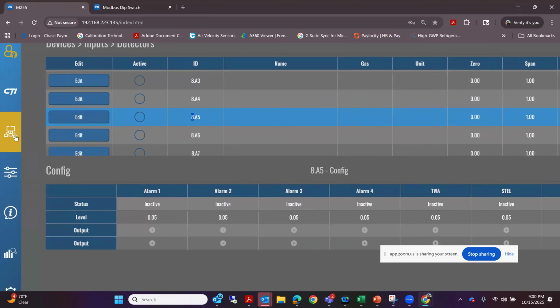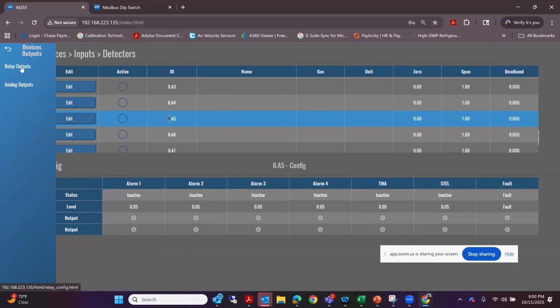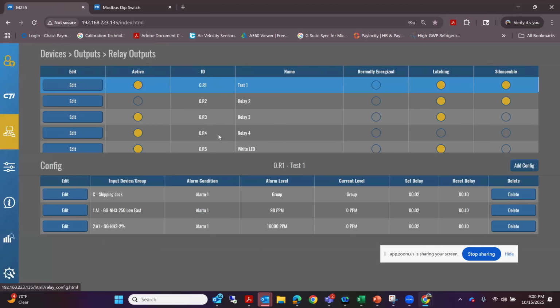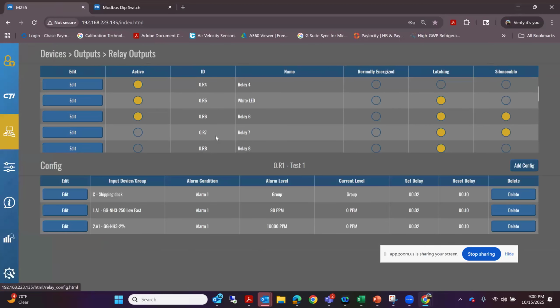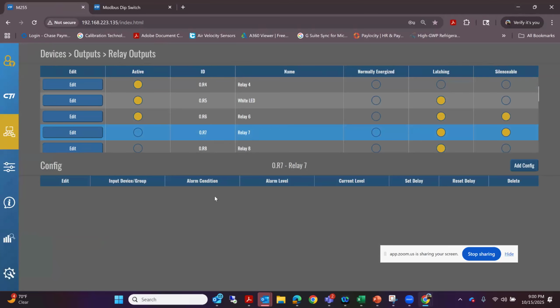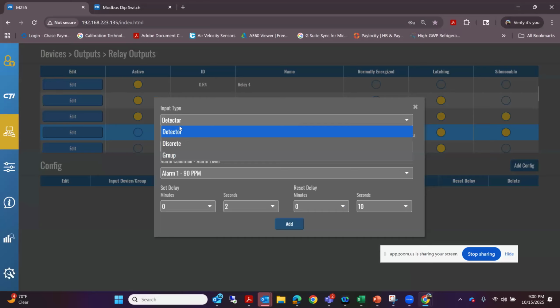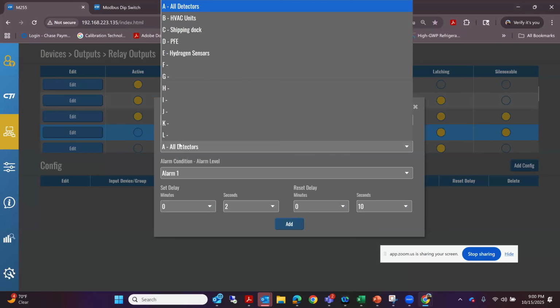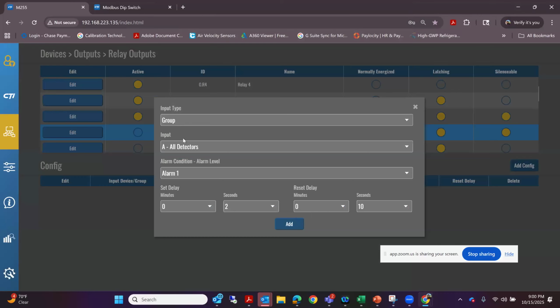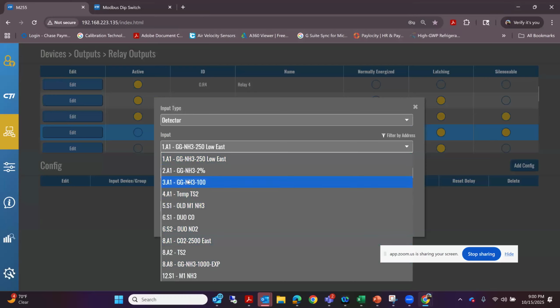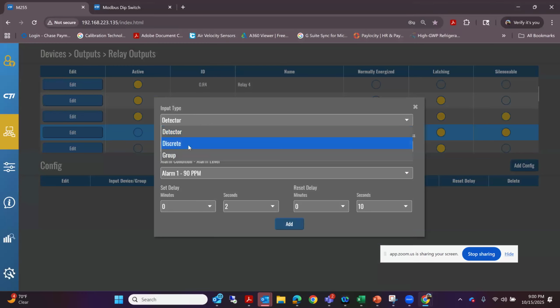So if we go like this and we want to look at the output relays, there's our 8 right there that are on board that we talked about. If I hit relay 7, I can see there's nothing configured for that one. So if I want to add that relay 7 and want to make it latching and make it silenceable, say that'd be a horn strobe assembly, I could say add configuration. I could choose the detector that's on the system, a group of sensors on the system, or I could just go to a specific detector on the system and it'll switch back to all the detectors that I have up there on that screen. And then I can say, okay, or I can do a discrete.